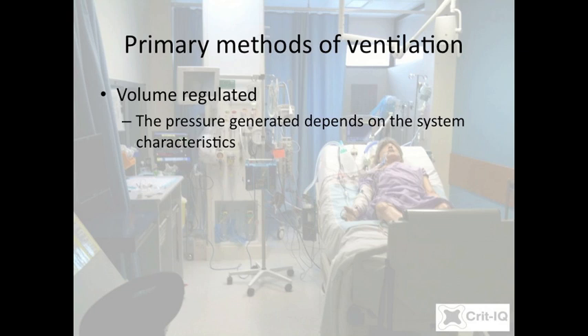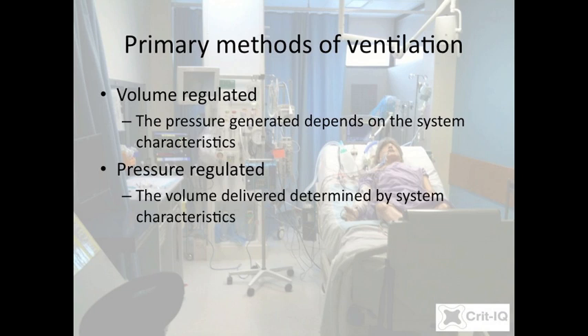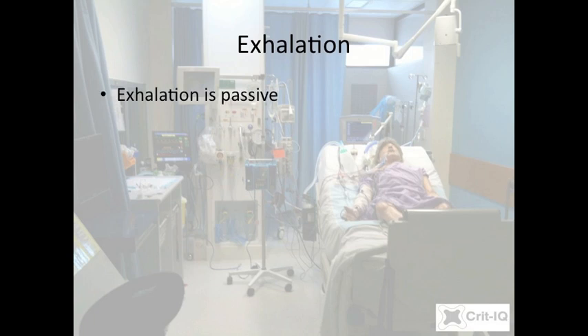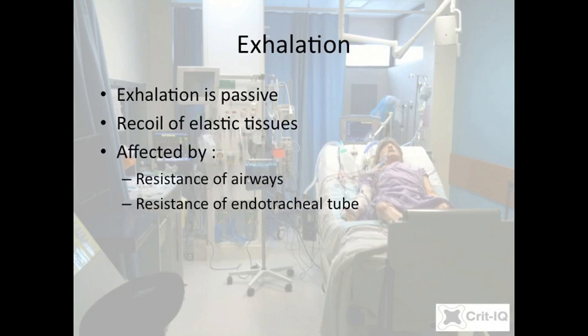In the second approach, the ventilator applies a pressure to the system, and the volume pushed in is entirely dependent on the same characteristics of the system. This is known as pressure-regulated ventilation, sometimes referred to as time-cycled, as expiration ends after a specific time. In either circumstance, exhalation is passive and relies on the elastance properties of the lung and chest wall, the resistance of the airways and the endotracheal tube, and some specific settings in the ventilator.